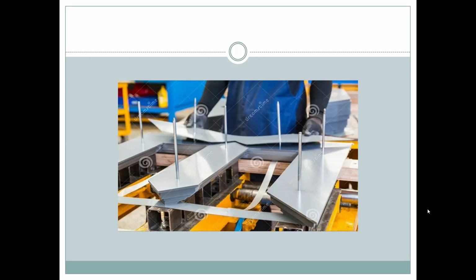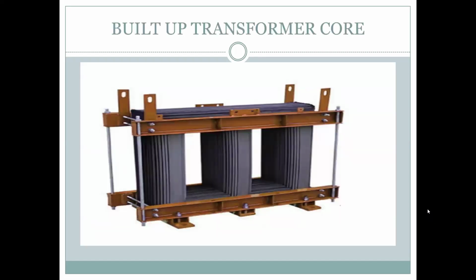You have to take the CRGO and place one after another horizontally by hand, and you have to build it. Whether it is a 350 MVA transformer or whatever, the core building is manual. And after building that core, as per design, it is to be made vertical. Now next slide. This is the level, the core is to be made. The first thing of the transformer.